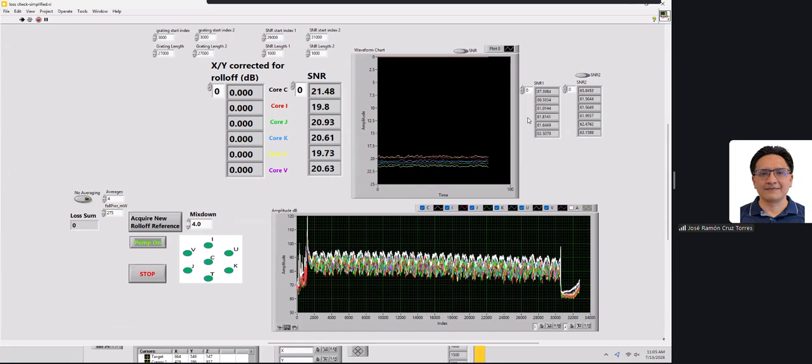This is also how we know, because every time a connector comes off the assembly line, or Chuck finishes assembling one, he will take data on how it performed with the golden sensor that he had, and then a lot of times we'll want to know how it performs on a bench with our setup and with a non-golden sensor.